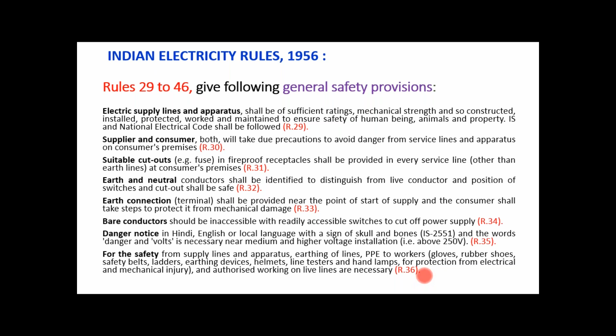Then rule number 36 is related to safety. For safety from supply lines and apparatus: earthing of lines, and personal protective equipment for the workers. In this case, gloves, rubber shoes, safety belts, ladders, earthing devices, helmets, line testers and hand lamps for protection from electrical and mechanical injuries, etc. So all these personal protective equipments are from the electrical accidents point of view. We have to reduce the chances of accident and the risk of electrical hazards, and from that point of view, these types of PPE should be used, which is necessary. So that is covered under rule number 36.